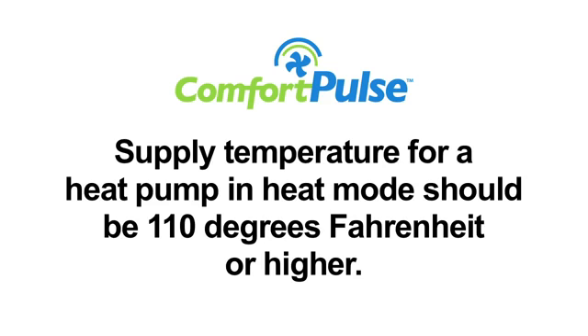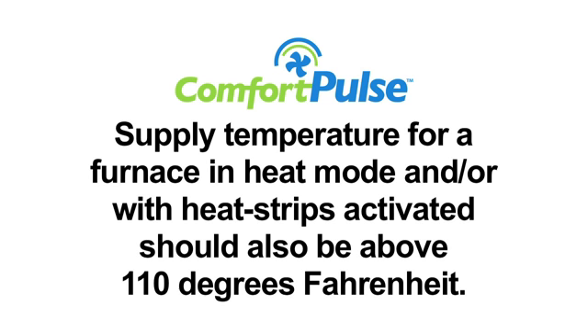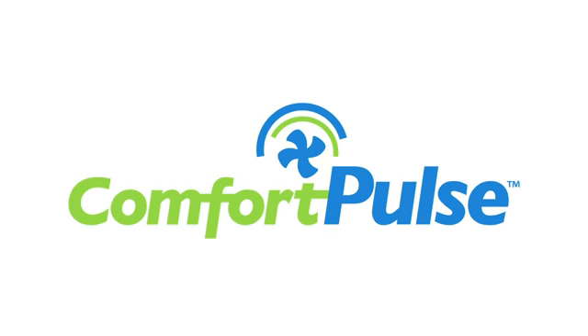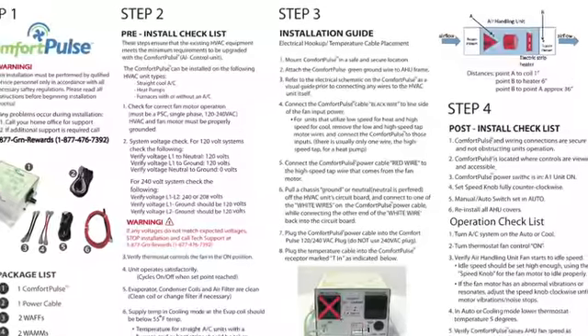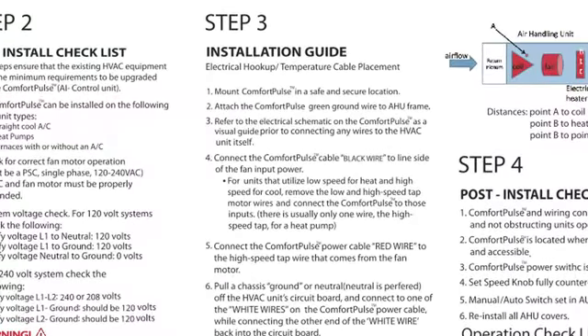Supply temperature for a heat pump in heat mode should be 110 degrees Fahrenheit or higher. Supply temperature for a furnace in heat mode and/or with heat strips activated should also be above 110 degrees Fahrenheit. If the temperature meets the requirements after checking the unit in both cooling and heating modes, you are ready to install the Comfort Pulse. Now we will address the electrical hookup and temperature cable placement procedures.